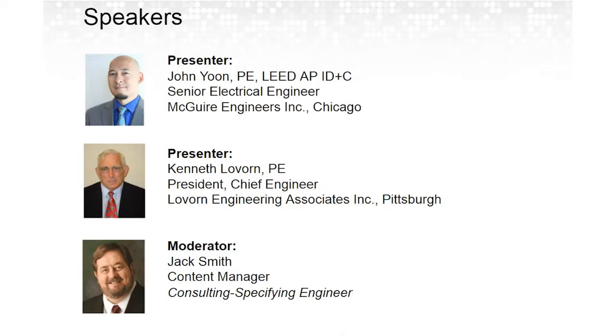You discussed the need to specify inverter duty motors and related power circuit features, such as input or output reactors, in order to successfully implement VFDs in building designs? Sure. This is a two-part question. One, we're talking about input to the VFD. So what we're addressing is power quality issues that use of the VFD may cause for all the other loads in the building. So in that particular type of situation, it's primarily based on an IEEE 519 evaluation, where you take a look at the overall transformer capacity and impedance and compare it to what you're adding in terms of the existing load or other loads in the building, and comparing it to the harmonic distortion caused by the VFD.